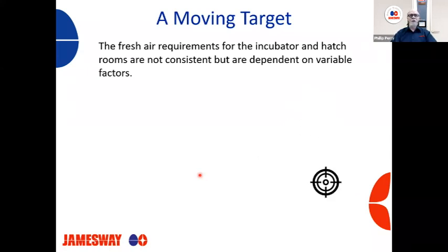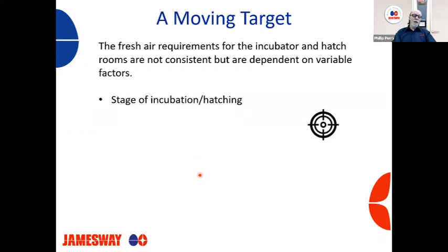Some of the older machines, I know the Petersime machines, had a raised hood that would collect exhaust, but it would also pull in outside air. So we had different ways of extracting that air. But now with the damper systems that we use, there are many things that can influence the amount of air and how we handle it.